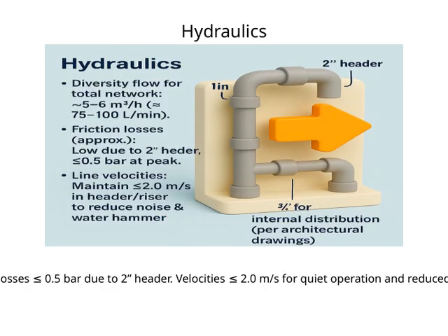Let's take a closer look at hydraulics in this system. The flow rate is typically around 5 to 6 cubic meters per hour, which is a solid, steady flow for efficient operation. Thanks to the 2-inch header, the pressure losses are kept quite low, less than or equal to half a bar, helping to maintain consistent pressure throughout the system. One of the key points here is velocity, keeping it at or below 2 meters per second. Why does that matter? Well, lower velocities contribute to quieter operation and help reduce water hammer, which can cause noise and even damage over time. Overall, these hydraulic parameters are designed to optimize performance, ensuring the system runs smoothly, quietly, and reliably as part of our larger goal to improve efficiency and longevity.